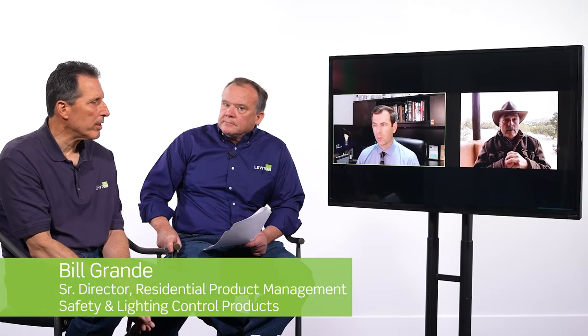Because electricians often would take one wire here and one wire there and connect it as neutral and try this. And then all of a sudden, these things are not sensing. And when they sense a miswiring configuration, they just won't turn on. And that's what we call a shared neutral condition, probably is what a lot of people would hear it as. And of course, on GFCIs, you could share the neutral as long as it's on the line side. So if you're going to take two hots and one neutral. But at that point, like you said, your pigtail splits it out, and they'll work fine.